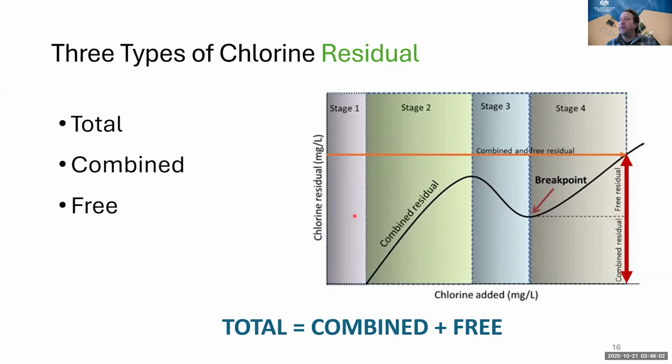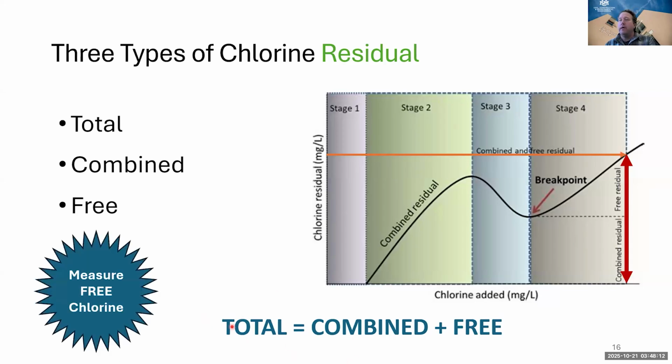Okay, so total residual equals combined plus free residual. And we can rearrange this equation however we want to solve for the unknown. When we practice free chlorine disinfection, we want to make sure to get to breakpoint.